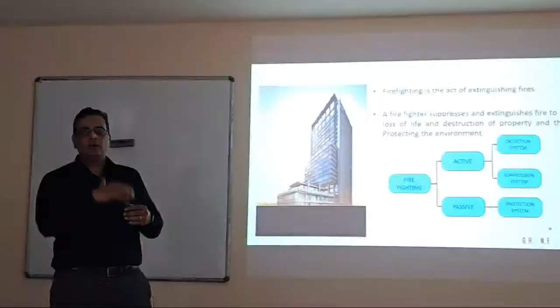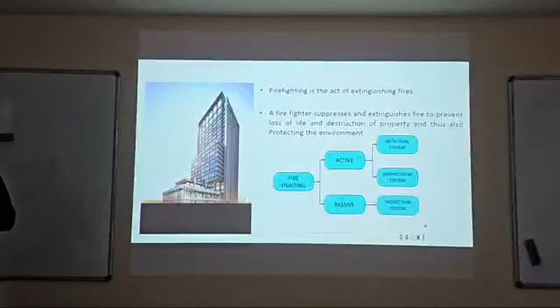I am able to design a smoke-free zone, a space where fire is not coming within my space, a space where I am safe till the time somebody comes and pulls me away. So that's your passive - your staircases, your codes, that 2-hour rating, 4-hour rating as per National Building Code. When you're doing your design, you will have this requirement.